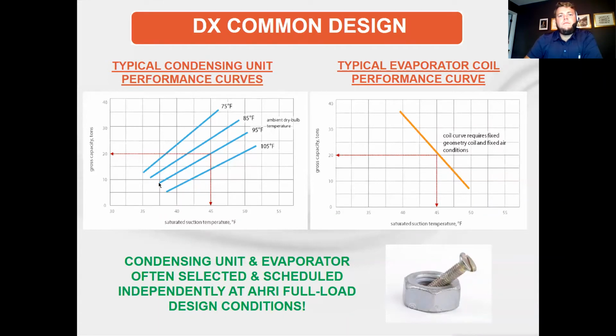And what this shows is that in this example, at 45-degree suction, this combination will give you 20 tons of refrigeration capacity. What it shows is as the ambient temperature increases, the capacity falls. That's because the compressor now has to lift the refrigerant to a higher state to get it above the ambient temperature to reject the heat at the condenser. It also shows that as the suction temperature falls, capacity is again reduced because the compressor has to do more work to lift it from a colder state to the higher state.